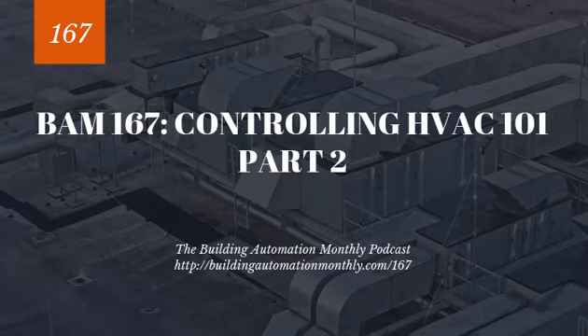So mixed air temperature control and outdoor air damper minimum position reset require new PID loops. And when you're circulating this air within a building, you have to be cognizant of how much air you're letting out of the building, how much air you're bringing in, and how much you're circulating. And that all affects your building static pressure.